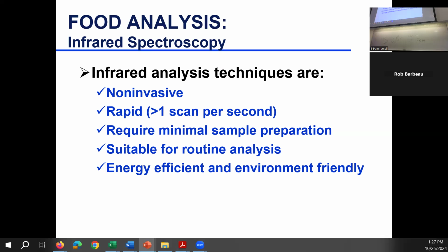Okay, so you want to calibrate the IR so that you have an unknown sample and you have standards. Let's say you want to measure fat content. So your standards have different levels of fat. Then you would say, okay, this is the concentration of the sample, you feed it, and then you run the calibration. You have a calibration, you run your unknown, and it gives you the fat content of 7. But how do we determine the fat content of the sample that we gave it?